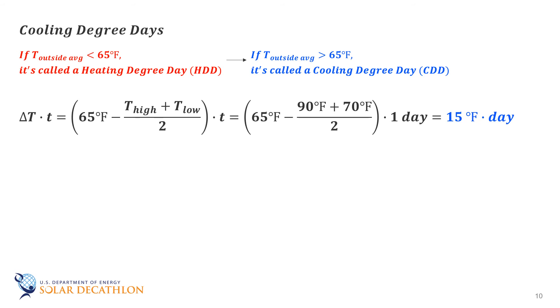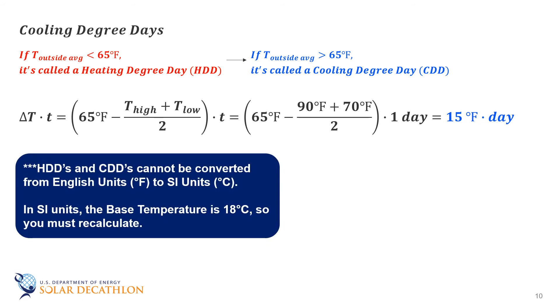A few other notes. You cannot do a unit translation with heating degree days from the English set of units to the SI units. You have to re-tabulate. Rather than use a base temperature of 65 degrees Fahrenheit, a base temperature of 18 degrees Celsius is used. These values are also widely available, including from the NREL Red Book. Other base temperatures are also used, such as 50 degrees Fahrenheit for growing degree days. This term is often used by farmers and gardeners.